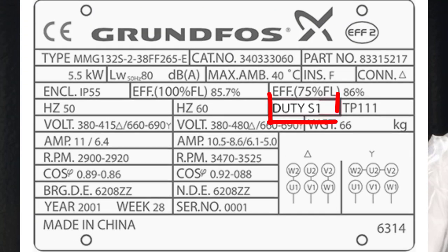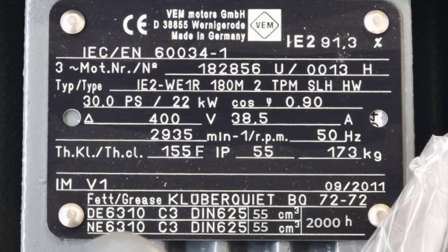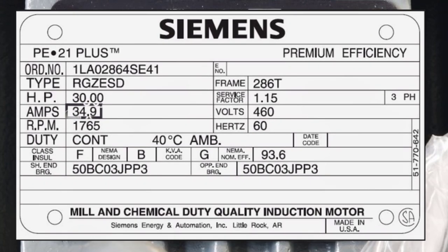The duty cycle describes whether the motor can run continuously 24 hours a day, 365 days a year, or if it operates on short-time or intermittent periodic duty. The service factor describes how much overload the motor can handle for a short period during normal conditions. For example, a service factor of 1.15 means the motor can draw 15% more than the full load current.